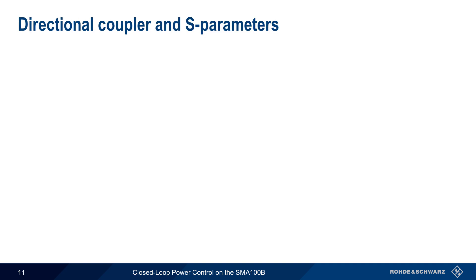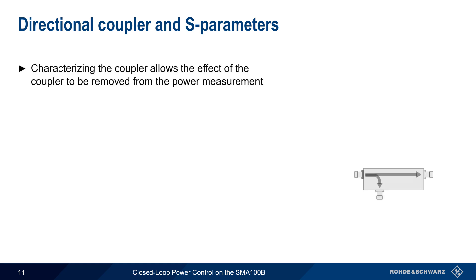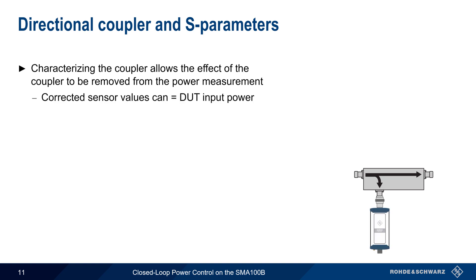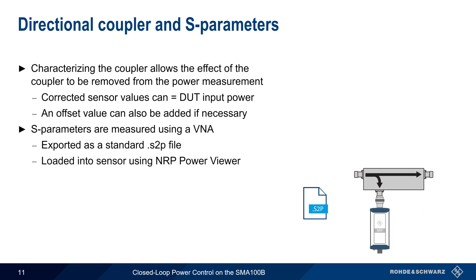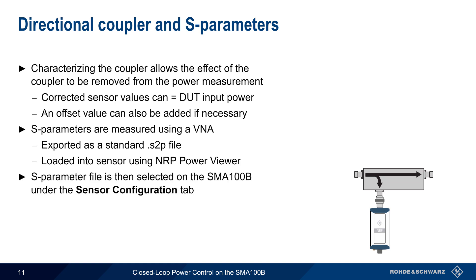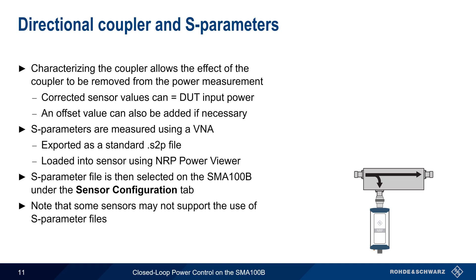Now let's look more closely at the role of the directional coupler in closed-loop power control. If we characterize this coupler, we can remove the effect of the coupler on the power measurement, and the corrected sensor reading will then display the same power as the power seen at the DUT input. An additional offset value can also be added if needed, to account for any fixed loss or gain between the coupler output and the DUT. We characterize a coupler in the form of S-parameters measured using a Vector Network Analyzer or VNA, and these S-parameters are exported as a standard S2P file. This file is then loaded into the sensor using the free NRP Power Viewer software package, and the appropriate S-parameter file is selected under the Sensor Configuration tab. Please note that some NRP sensors may not support the import of S-parameter files.